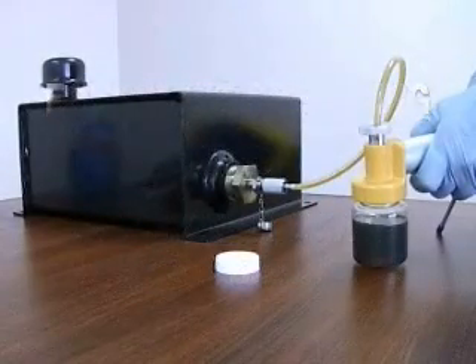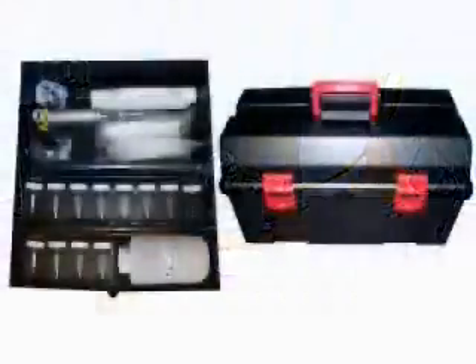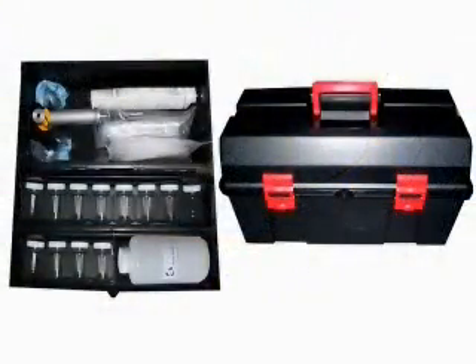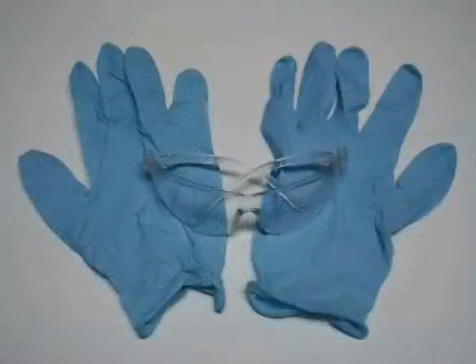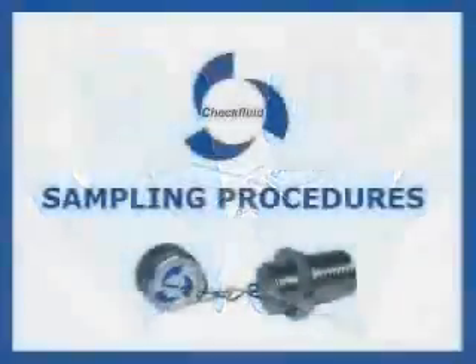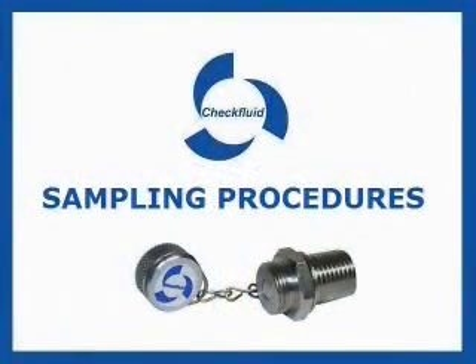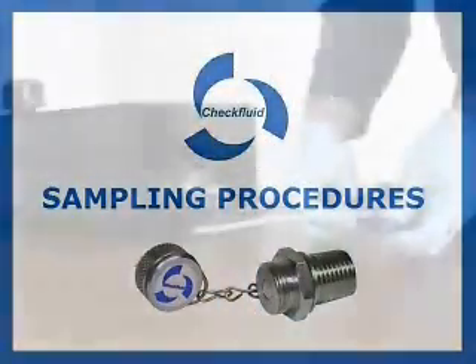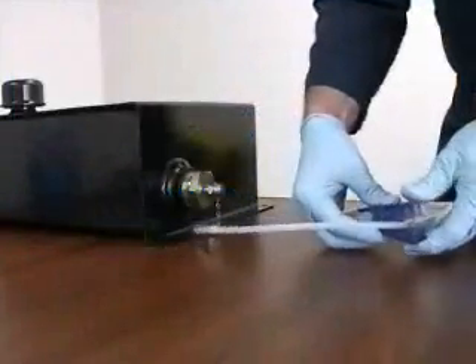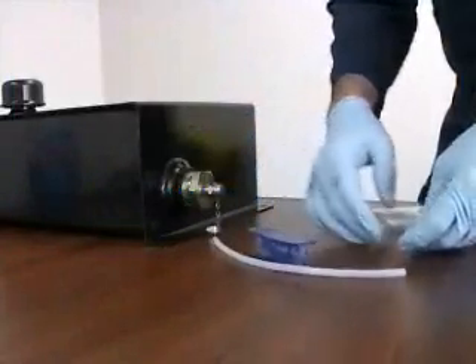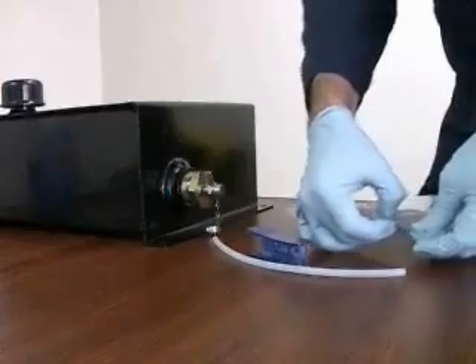sampling. Ensure that all supplies are on hand. Nitrile gloves and safety glasses protect against accidental contact with hot or pressurized oil. Cut a length of tubing as long as necessary to reach the sampling bottle. Reseal the tubing bag to prevent any contamination.